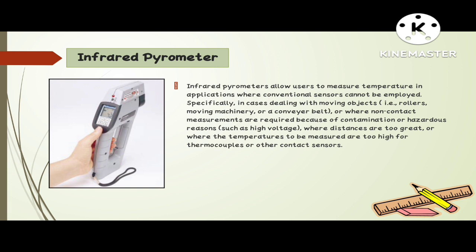Infrared thermometers usually use a lens to focus infrared light from an object onto a detector called a thermopile. The thermopile absorbs the infrared radiation and turns it into heat. The more infrared energy, the hotter the thermopile gets. This heat is turned into electricity. The electricity is sent to a detector which uses it to determine the temperature of whatever the thermometer is pointed at. The more electricity, the hotter the object is.